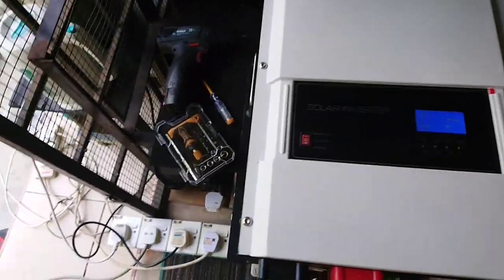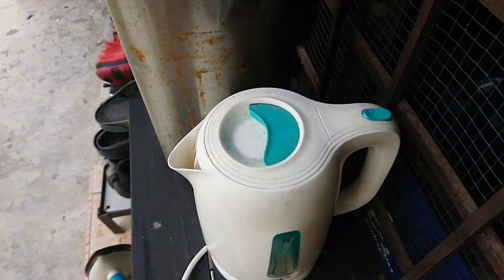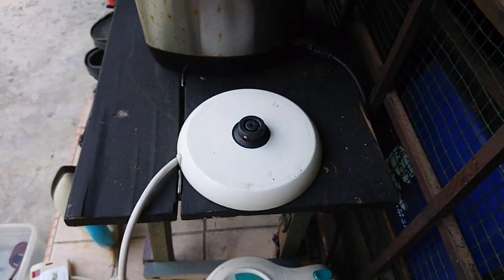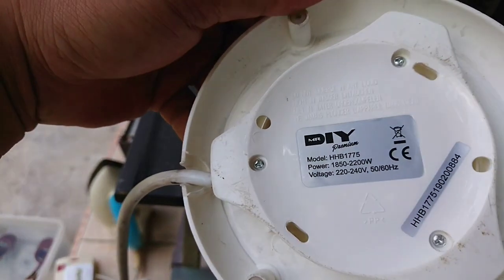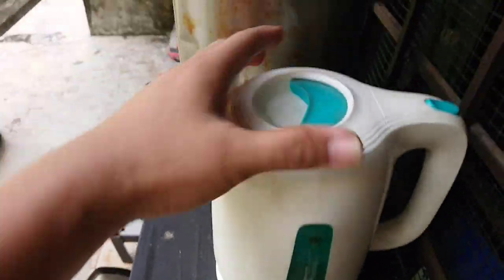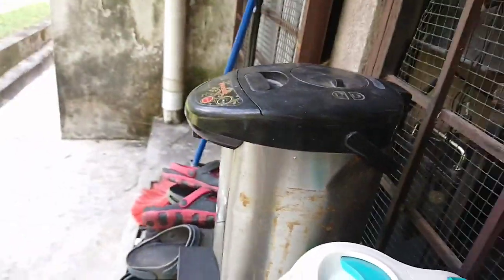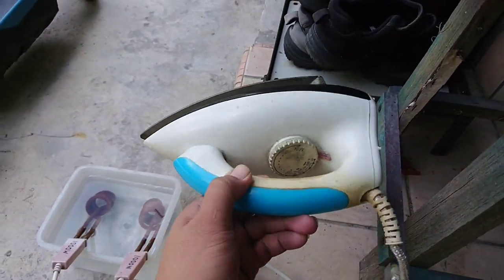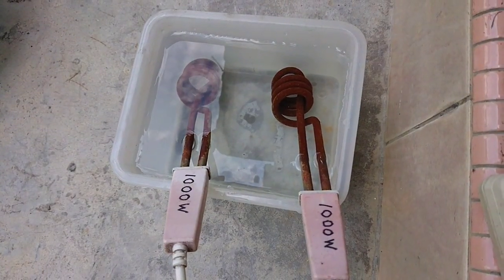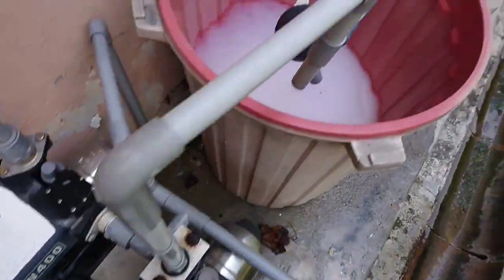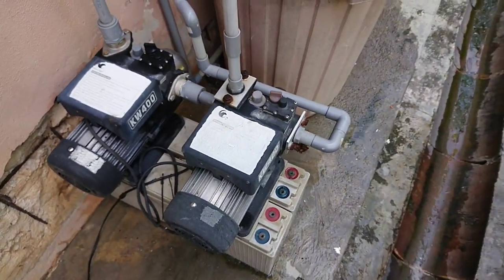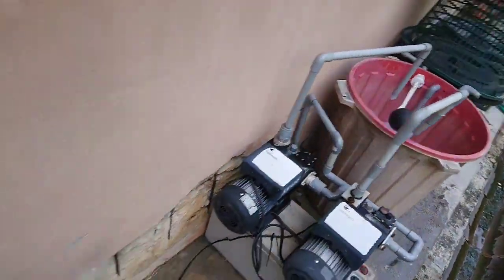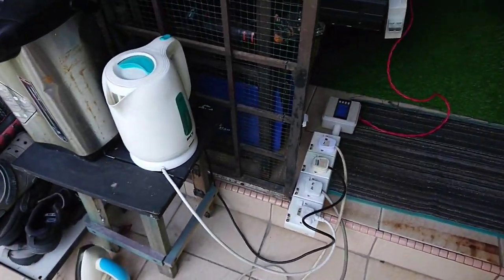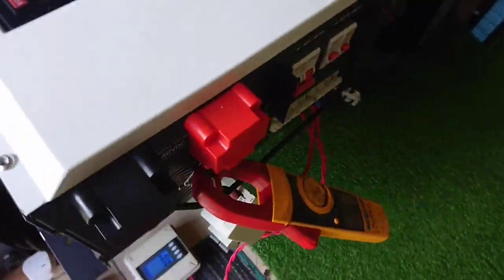For the full load test, I will push the Growatt over 6kW. Today my load is a 2.2kW kettle, a 750 watt thermal pot iron making it 1 kilowatt, two heaters at 1 kilowatt each making 2 kilowatt, and two water pumps, 1 horsepower total each. So I will turn everything on together, over 6kW, and see how many amps the Growatt takes.